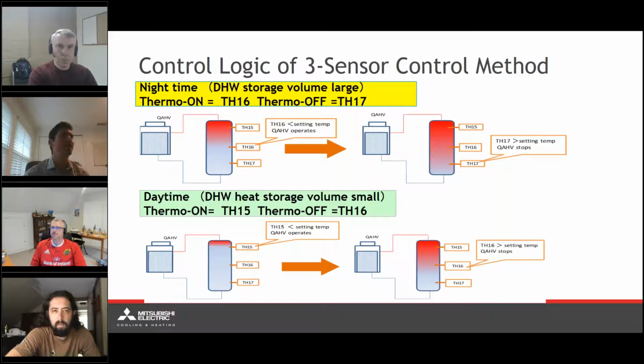the QAHV is just going to be cycling on all day, and it's not going to be operating in its most efficient state. Most efficiently, this is going to be maintaining an appropriate amount of water in these tanks. It's not going to be utilized as an on-demand heating. We're just going to make sure we have enough hot water on hand.